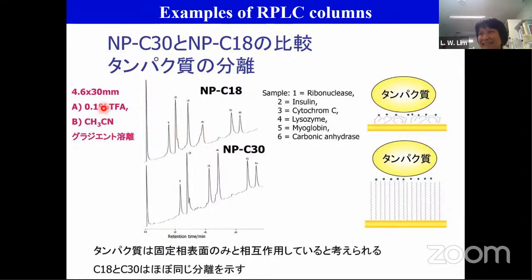For example, this one is a hydrophobic column, so we use a buffer. For example, this is a gradient elution using different buffers. In order to clean this column, usually I will use methanol, depending on the polarity of the column. If it is a hydrophobic column, the hydrophobic compounds will be absorbed so strongly they never want to come out.